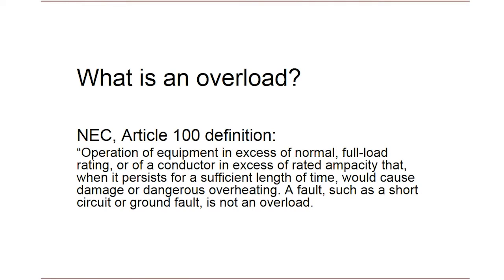When we talk about unintentional or objectionable current, we're typically talking about either overloads or faults. The NEC definition of an overload essentially says that current flow in excess of normal full load rating that persists for a sufficient length of time would cause damage or dangerous overheating. Note that this is current flowing through the circuit through the normally expected path, but in excess of what the components in that circuit are rated for. This could be sustained locked rotor current associated with a seized motor, or too many appliances plugged into one circuit.